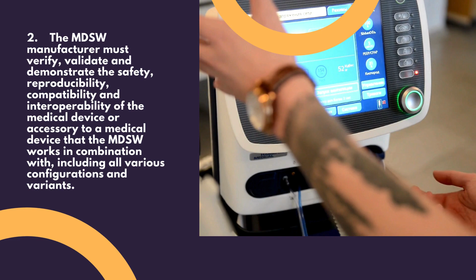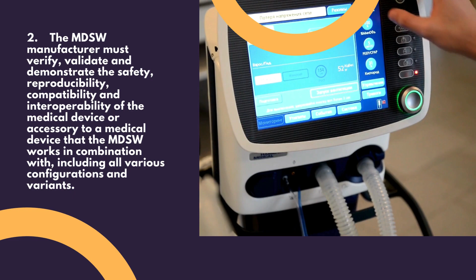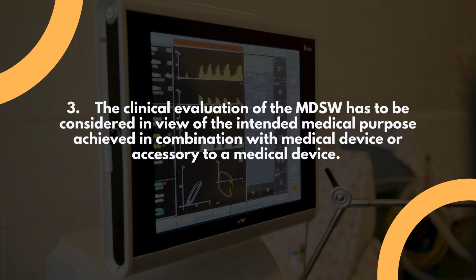Number 2, the medical device software manufacturer must verify, validate, and demonstrate the safety, reproducibility, compatibility, and interoperability of the medical device or accessory to a medical device that the medical device software works in combination with, including all various configurations and variants. Next, the clinical evaluation of the medical device software has to be considered in view of the intended medical purpose achieved in combination with the medical device or accessory to a medical device. Followed by the hardware components, which act as medical devices or accessories to a medical device.